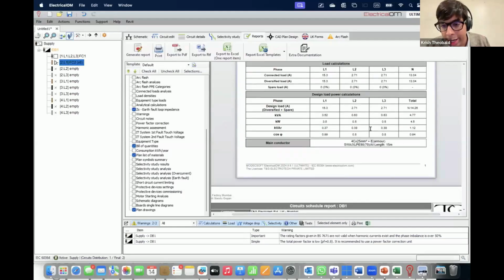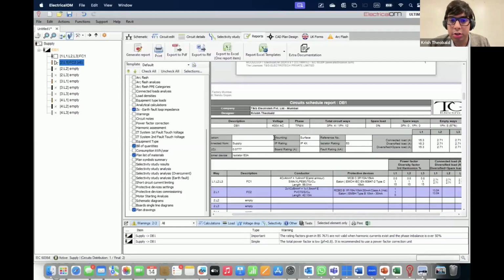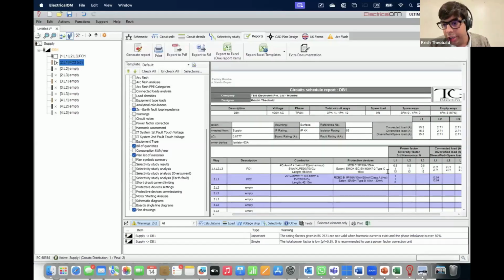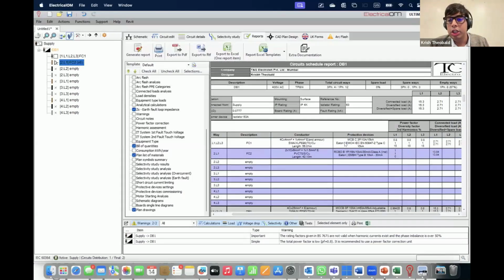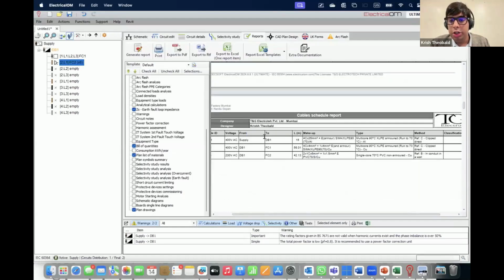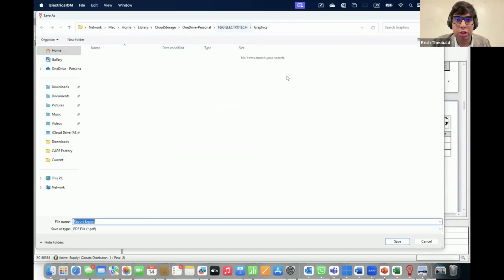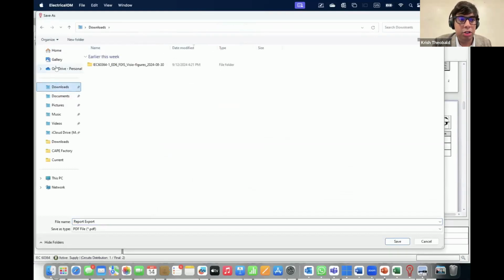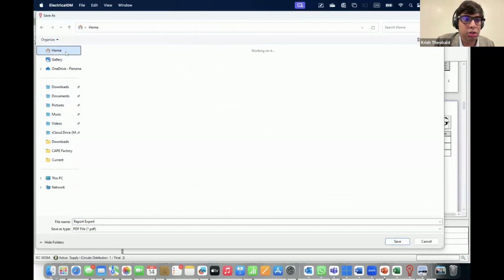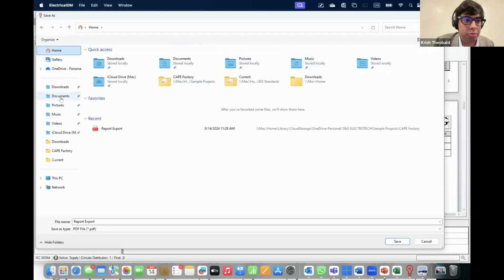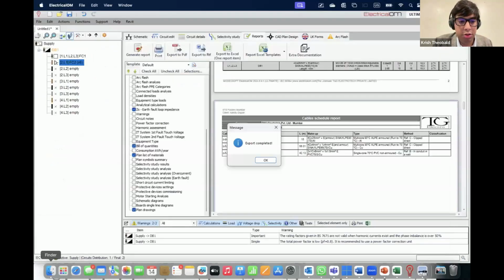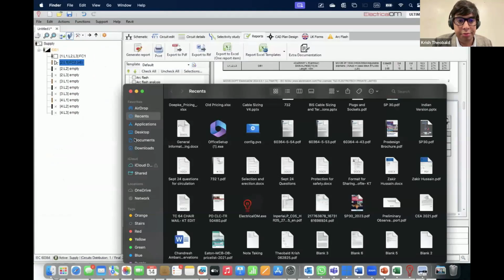So it gives me the supply characteristics. It tells me, these are the final circuits. These are the power factor harmonics. This is the load. If you want to add a diversity factor, any spare capacity. These are the cables that we are using. How are they installed? So actually, I will export to PDF so we can actually see it separately. Documents, report, export. Export complete. There you go.